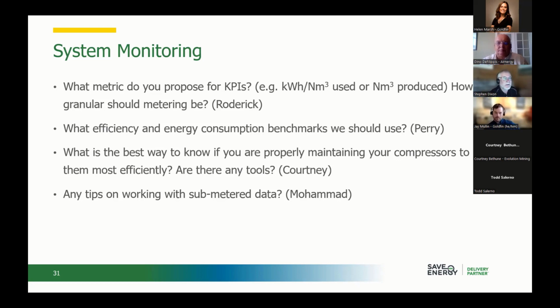All these things are great, they all have a different purpose. Looking at energy KPIs over time kind of looks at the overall energy efficiency of your system. Looking at the instantaneous, like kilowatts per 100 CFM, that looks at what you're operating at now at any point in time, and then looking at the flow at any point in time as well. I think all three of those are useful, as long as people are looking at them, and there's a means or a protocol for them to respond.